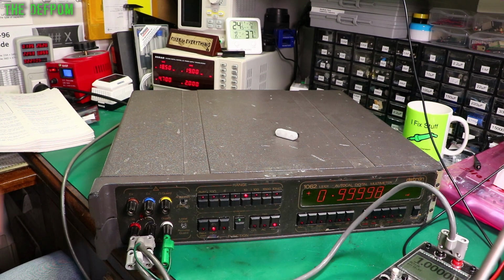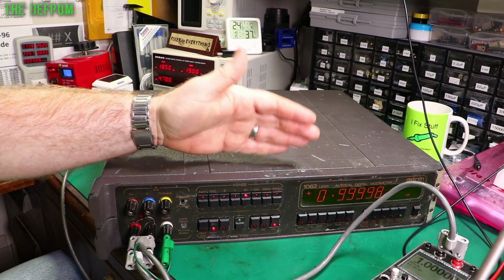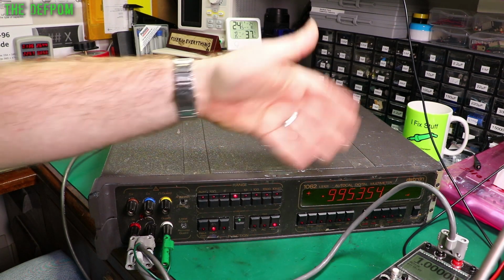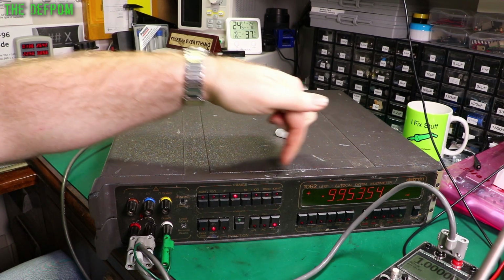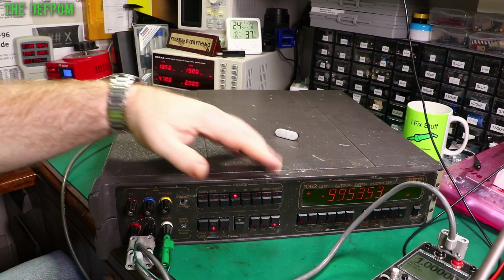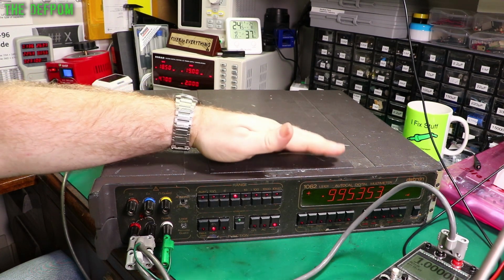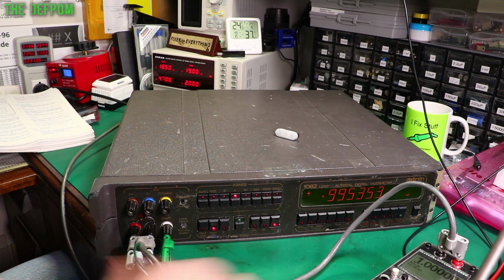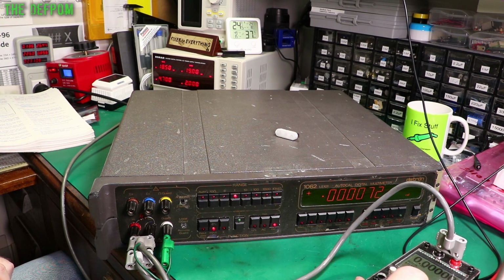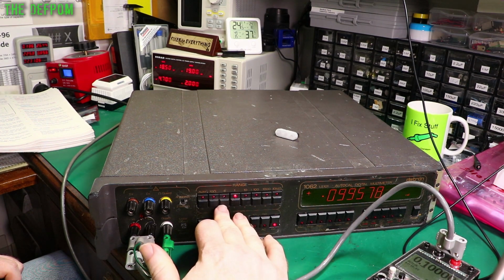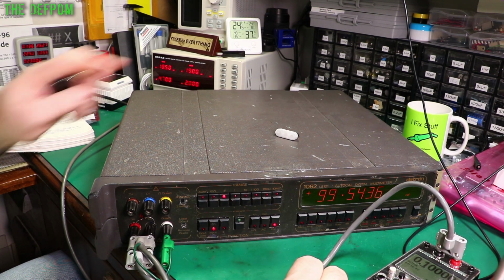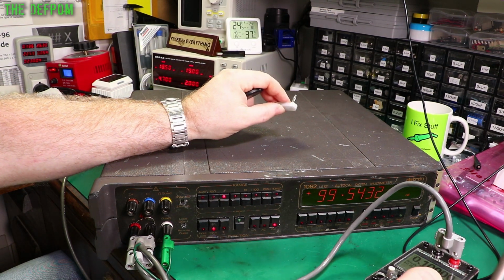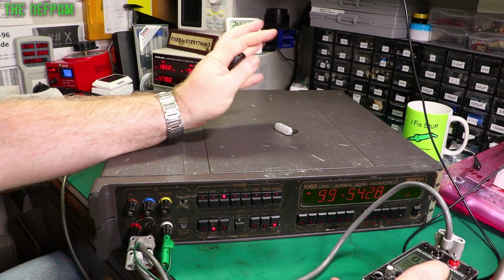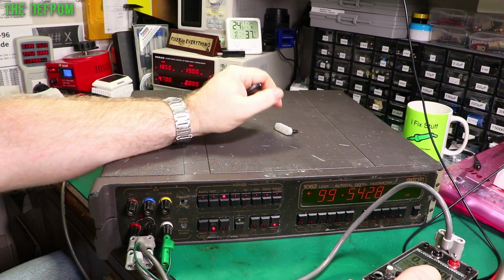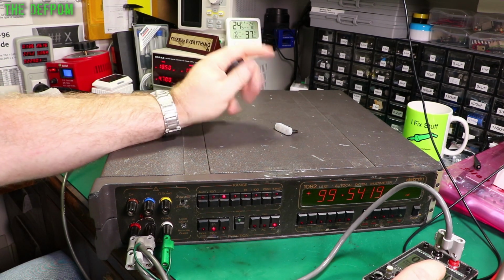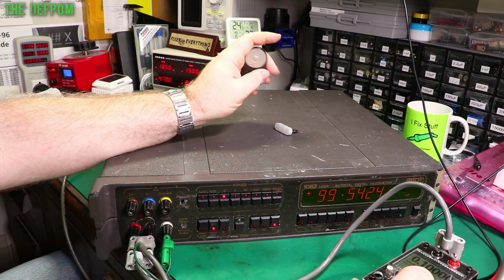It doesn't need changing. So what this means is I'm going to have to go through and do a calibration on the unit, because although I've done that adjustment on the 10 volt range as per the instruction manual over here, the 1 volt range is wrong still, and I was hoping that would be corrected by what I've been doing. Obviously that's not the case. If I do 100 millivolt range, same deal. So I'm going to have to go through and do calibration. It must have lost the calibration constants at some point, or someone's reset them or something, because obviously just doing that adjustment hasn't done the job. So, and that was what I was hoping to fix it, and it's not been that. So I'm going to have to go through and calibrate it. That's not a big deal.